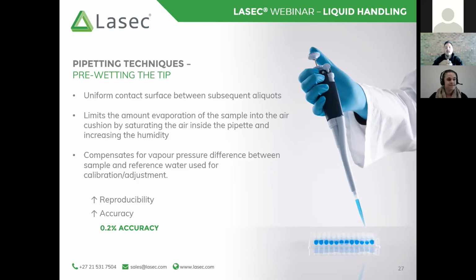Okay. Again, going back to the principles of air displacement pipettes and how they work with the air space between the piston and the sample. Like I mentioned, this is a micro environment and it is subject to change. All right. So by pre-wetting that tip, generally speaking, we recommend that you pre-wet at least 3 times. Essentially what you are doing, say, for example, you are using a hot sample versus a cold sample, you are priming that environment inside of the tip so that it's accurate between subsequent aliquots.